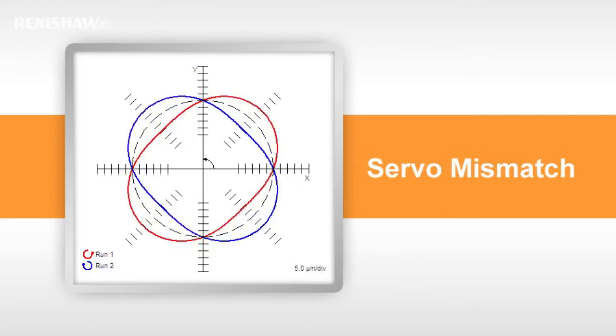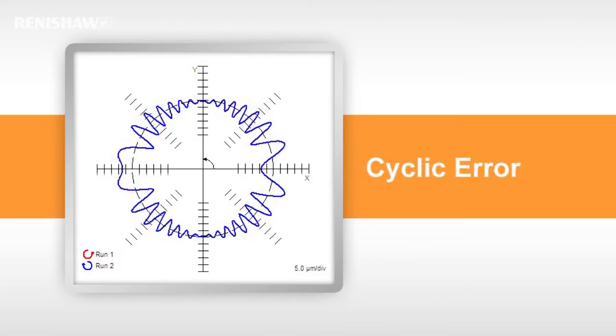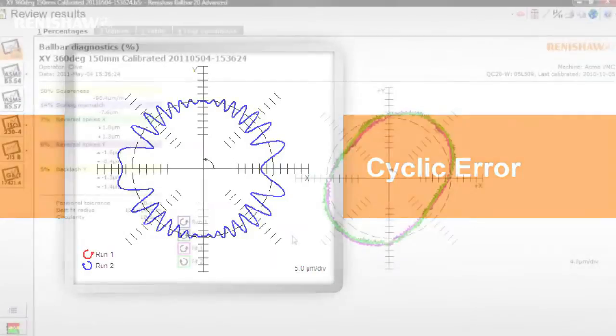Servo mismatch. Note how this looks similar to squareness, except that the forward and reverse runs mirror each other. Cyclic error appears as a sinusoidal error, varying in both frequency and amplitude around the plot.